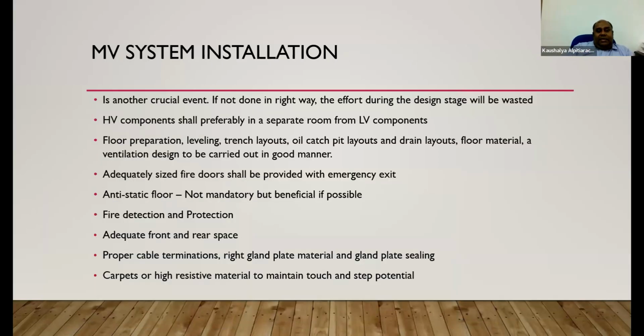ME system installation is again a very crucial event. If that's not been met, definitely your effort during the design stage will be wasted. So time is reaching the end, and I will have to rush through this. HV components shall preferably be in a separate room from LV components. Floor preparation, leveling, trench layouts, oil catch pit layouts, drain layouts, floor material, and ventilation design are to be carried out in a very good manner.